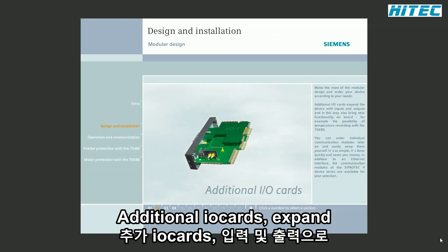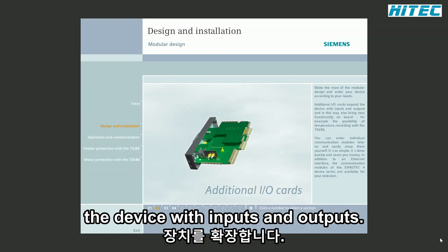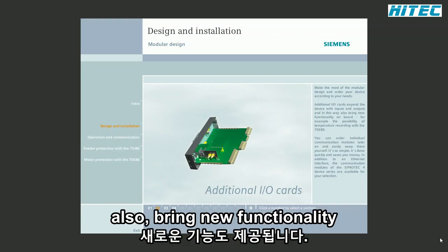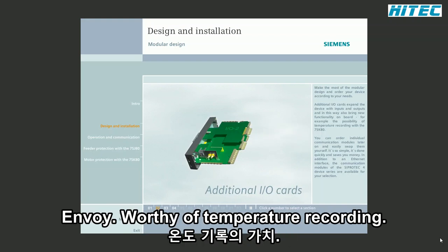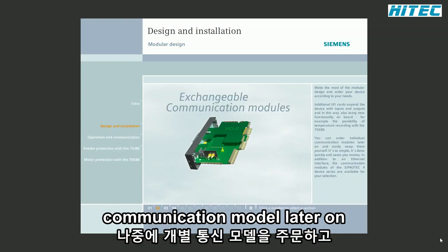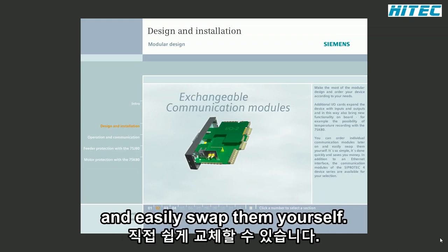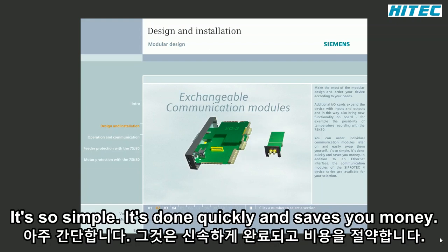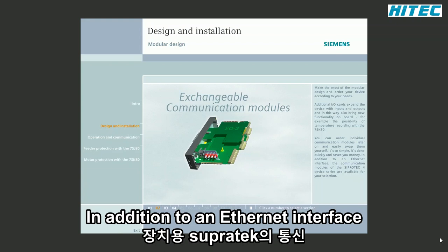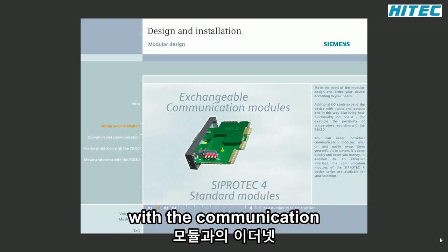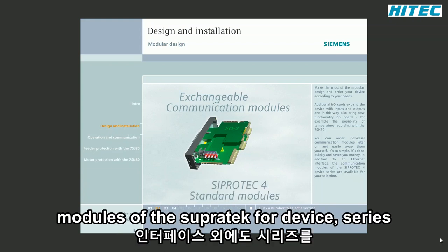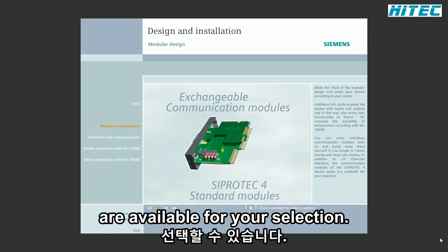Additional I/O cards expand the device with inputs and outputs, and in this way also bring new functionality on board, for example, the possibility of temperature recording with the 7SK80. You can order individual communication modules later on and easily swap them yourself. It's so simple, it's done quickly and saves you money. In addition to an Ethernet interface, the communication modules of the SIPROTEC 4 device series are available for your selection.